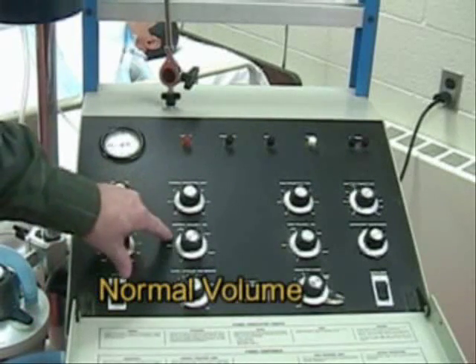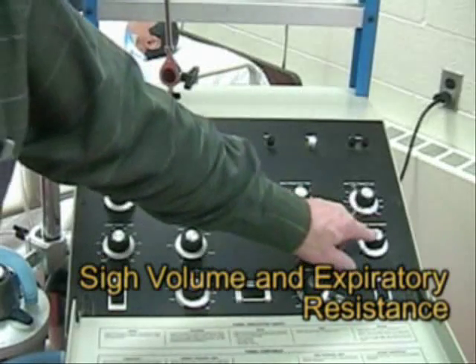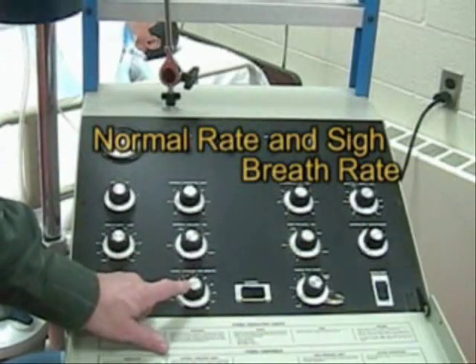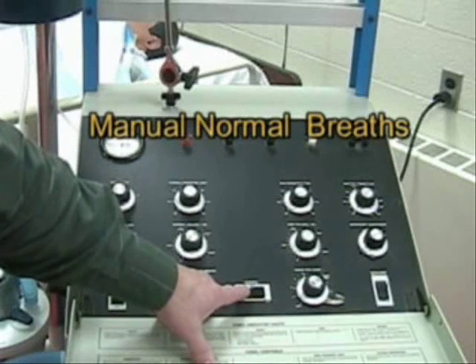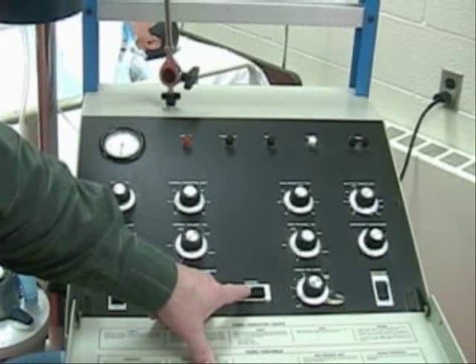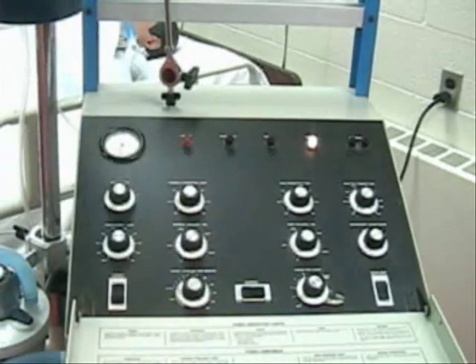Normal volume is our tidal volume. Then we have Sigh Volume, expiratory resistance, the rate in cycles per minute, and Sigh breaths. We also have a normal breath button — we can give an extra breath in between the machine breaths. Or we can give a Sigh breath, which is a larger breath.